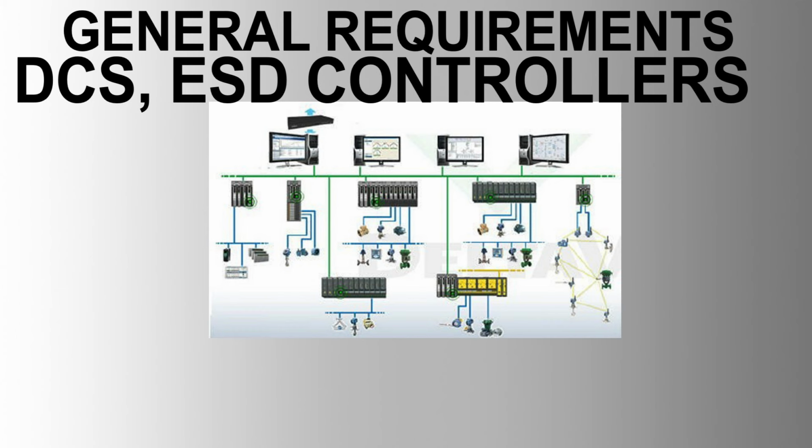First-up alarm and sequence of events, SOE. A facility-wide sequence of event recording function shall be provided, with timestamping done in the DCS, and a first-up alarm identification implemented in the ESD. The system should provide dynamic cause and effect, including overrides and resets displayed on the DCS operator interface.